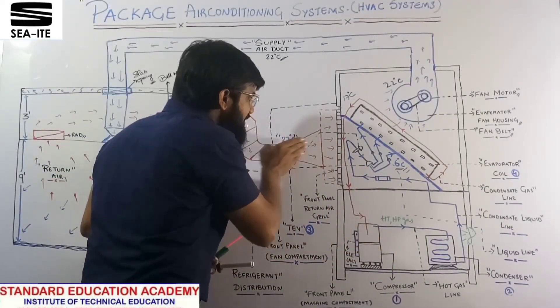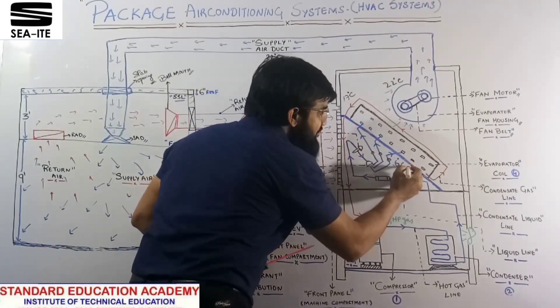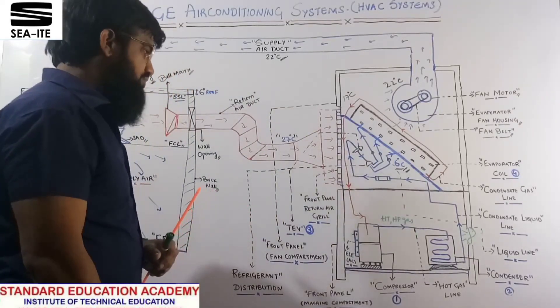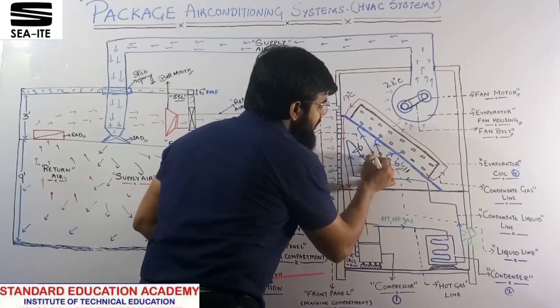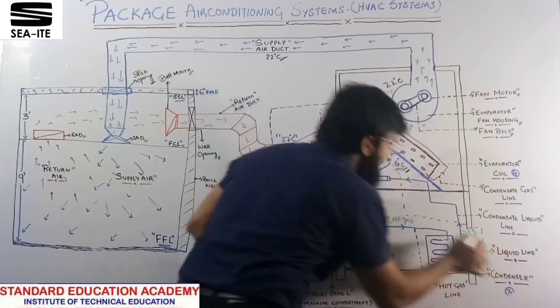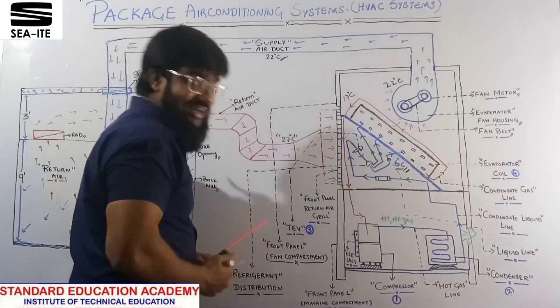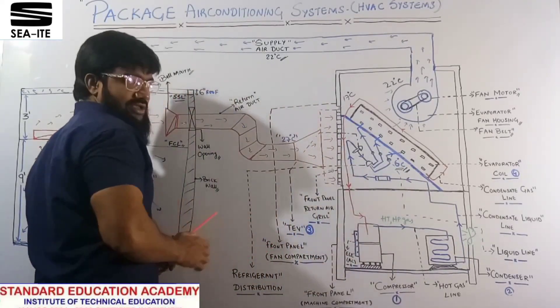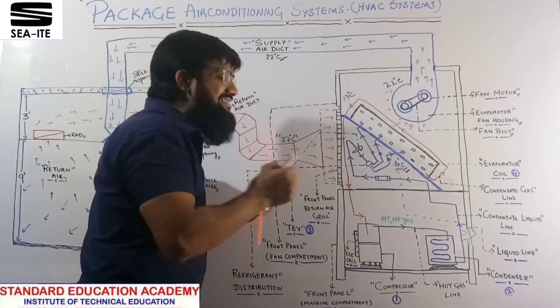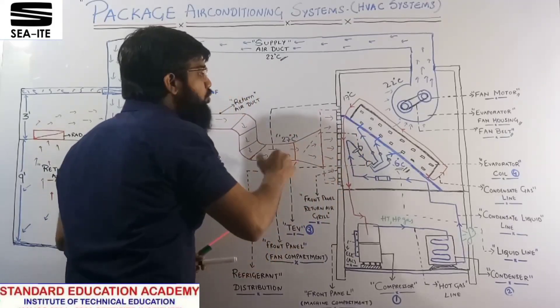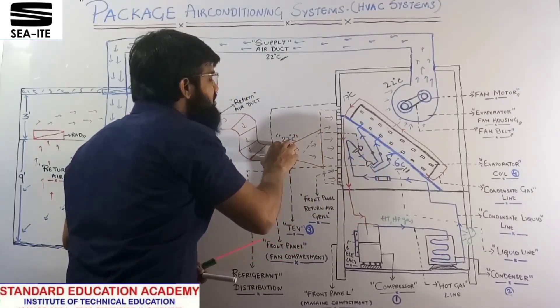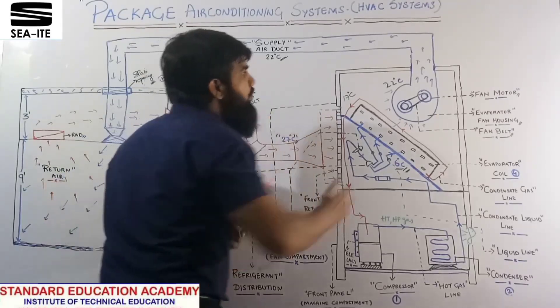As the return air comes in at 27°C, the refrigerant is distributed at a temperature of 6°C in liquid state. This is a liquid line. Return air at 27°C meets refrigerant at 6°C, so the return air rejects its heat to the liquid refrigerant. As a result, the air temperature converts from 27°C down to 22°C.